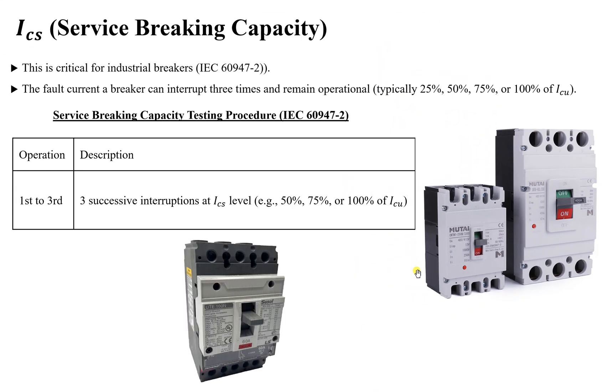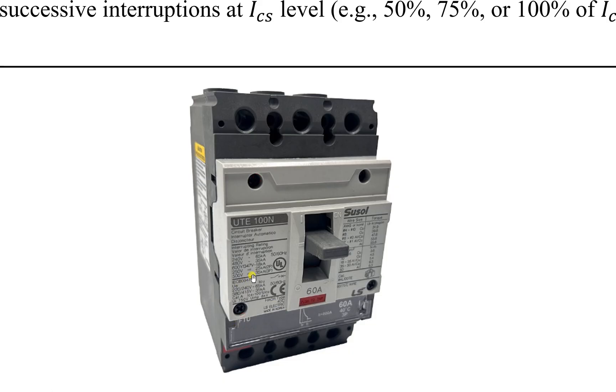The reason ICS is lower than ICU is cost. If we designed the breaker to interrupt the maximum fault current several times, it would be very expensive because it must withstand that full fault current repeatedly. To save on design costs, we have a breaker that can interrupt the worst case at least once, and interrupt a lower value several times.